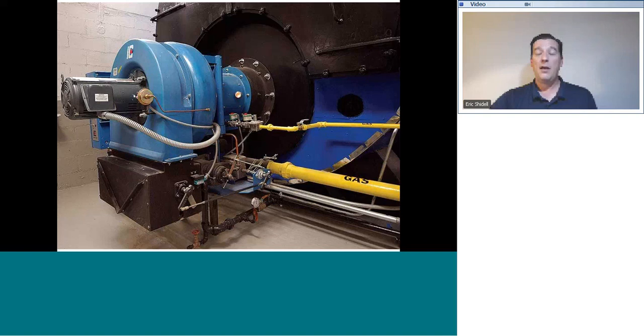These pilot burner solenoids will open, sending gas to the pilot burner. A spark will happen. Pilot flame will be established and proven. Then, next, the main gas valve will open. But because this damper is closed and this valve here is almost all the way closed, the main burner will be established with just a very small level of flame.